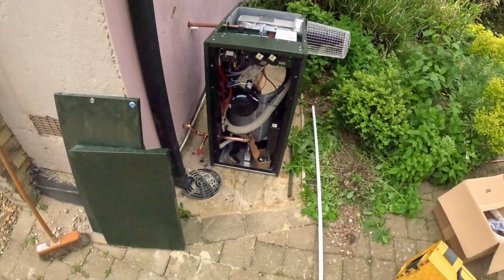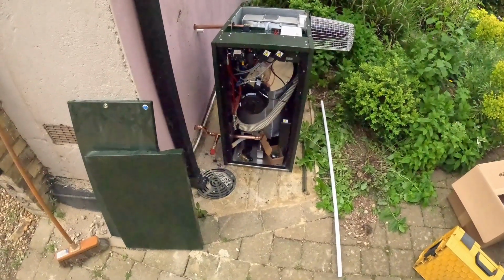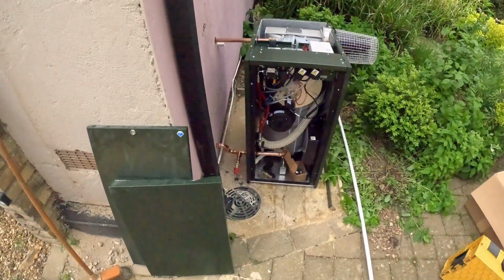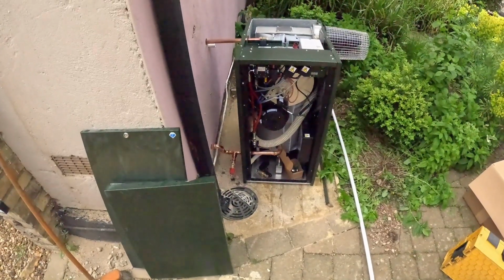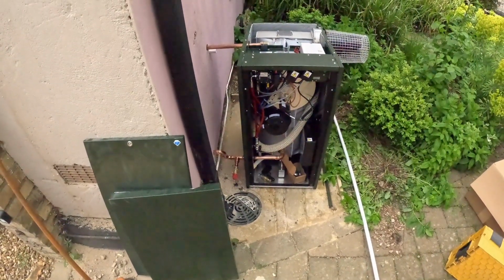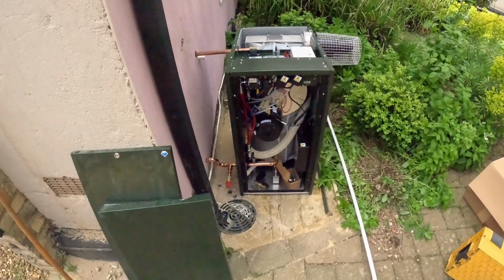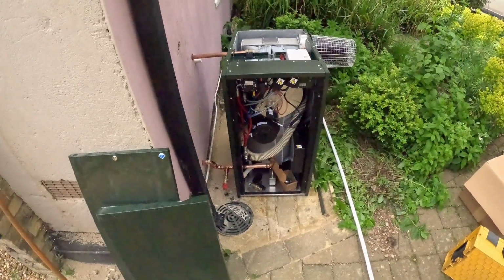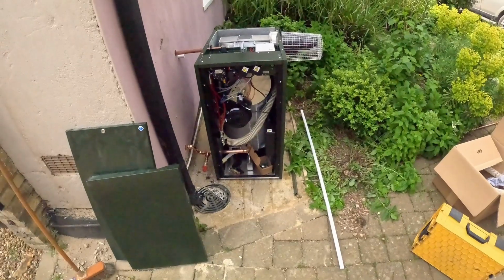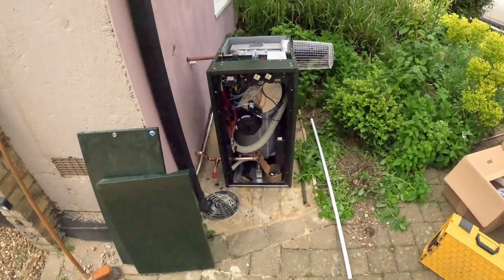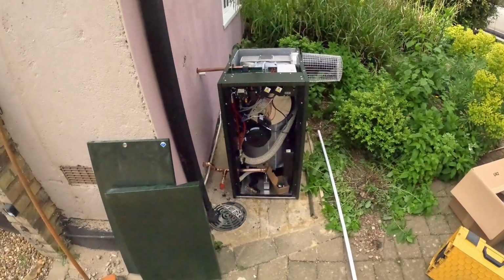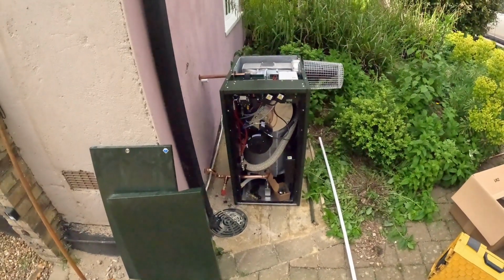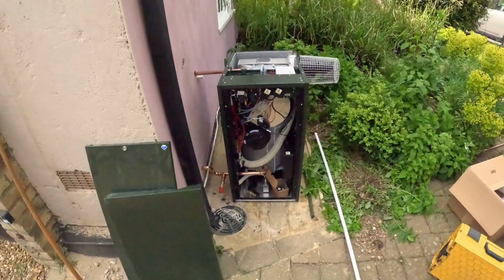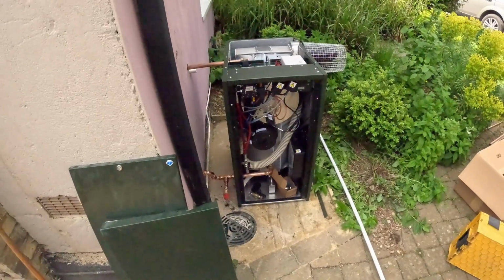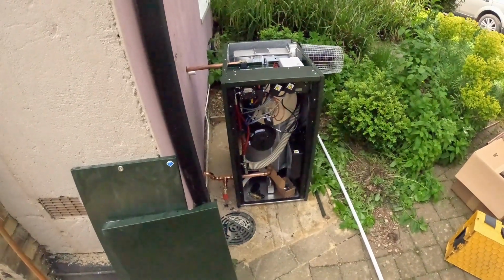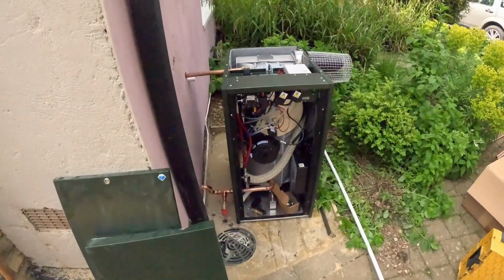So that's just about done for today. Having a good pack up. Coming back tomorrow, we'll get the oil line done first thing, get the system filled up since it's pretty much ready to be filled now, get it wired, give the lads at EOGB a ring and see when they can come down and help us out, and then that'll be the next video. It'll be commissioning time, and we'll see how it all gets running, how the open therm controls can modulate the state of the boiler, and then we'll run you through how we plug in the EOGB Sapphire control box that you get when you're a service agent, and how to set up the burner and the pump.